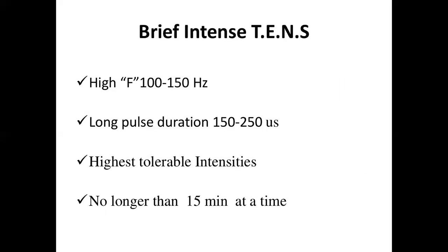Next up, brief intense TENS. It is high frequency, up to 100 to 150 hertz, with long pulse duration of 150 to 250 microseconds, highest tolerable intensities, and no longer than 15 minutes at a time.